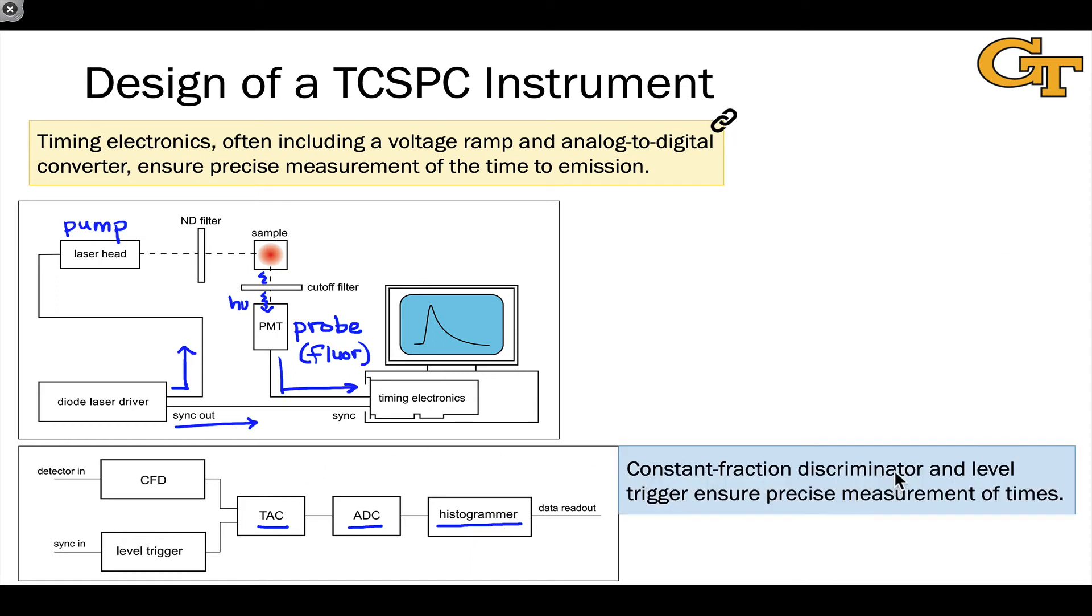To ensure the precise measurement of times, we make use of this constant fraction discriminator or CFD and the level trigger. And the idea here is that the PMT will give somewhat different responses for each photon that hits because of slight variations in how the fluorescence process takes place and how the photomultiplier tube detects a photon impinging on it. And so we essentially use a cutoff level to detect that a photon has been emitted in the case of the CFD. And in the case of the level trigger, that an excitation photon has been sent to the sample via the laser. When that level trigger hits, that's our start signal, our indicator to start the stopwatch. And when the CFD hits, that's our stop signal. Since the photomultiplier tube is now giving us a signal and CFD tells us, yes, that's a real signal, stop your stopwatch.